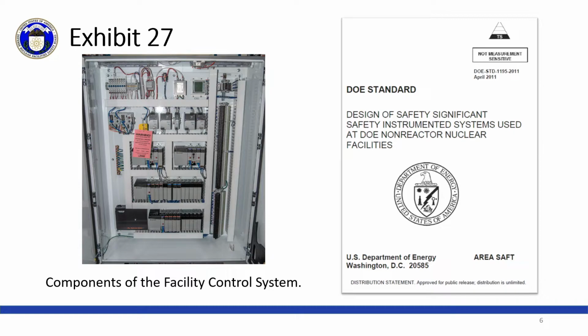Triad is working to replace the logic controllers for the facility control system, which is a safety significant system. We understand Triad concluded that its effort did not need to follow DOE Standard 1195, which covers safety significant systems, because the scope of the upgrade was limited. However, future efforts are planned to replace sensors and actuators, and in total, when you put the pieces together, these upgrades constitute a full safety instrumented system for which the standard was intended to apply.